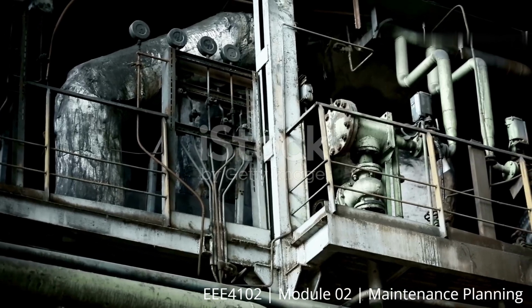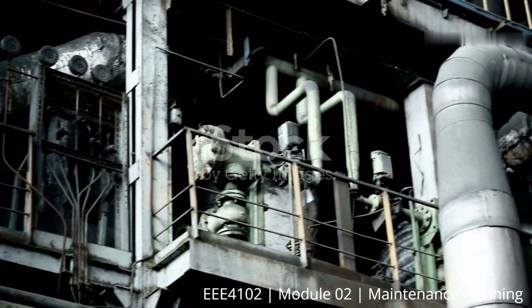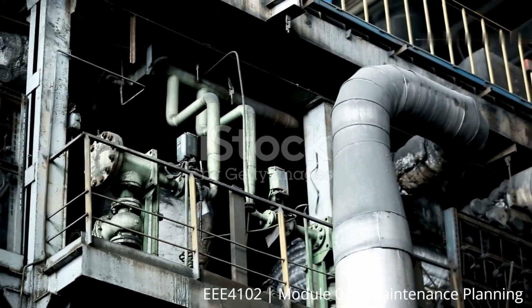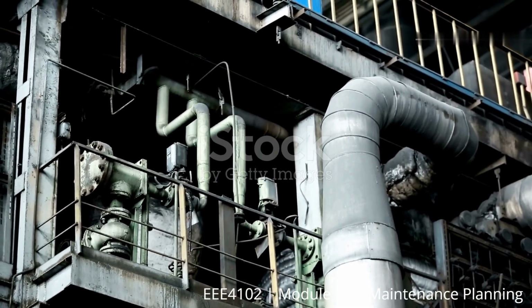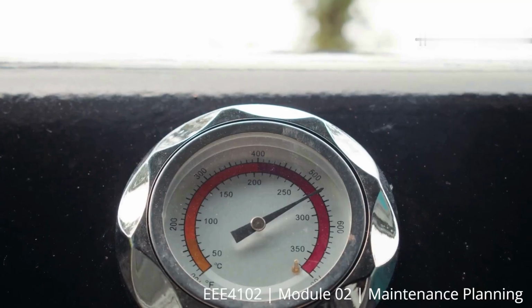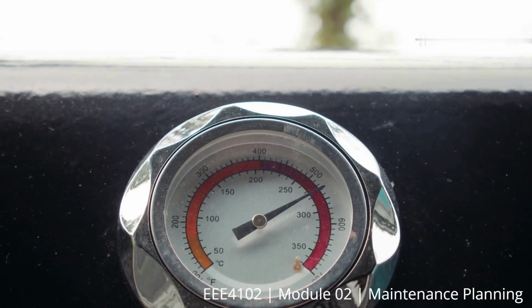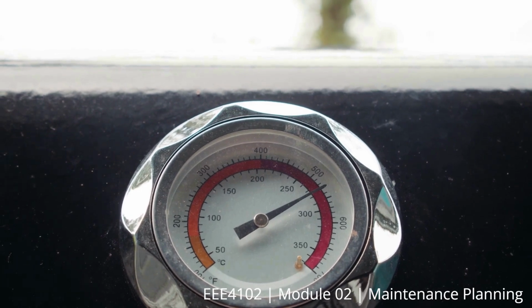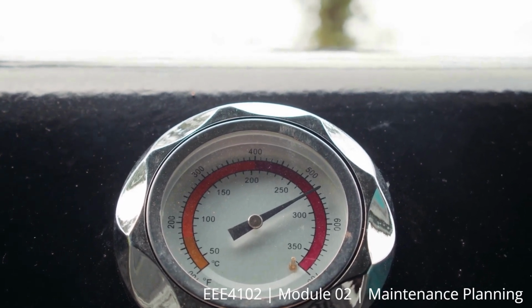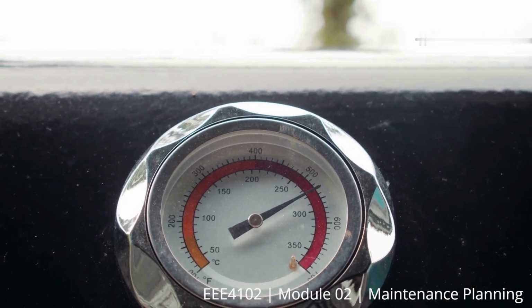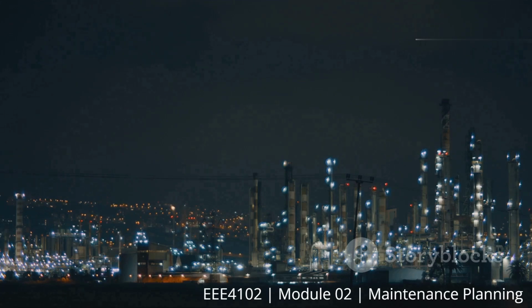Let's consider a real-world case study. Imagine a large power generation facility. During annual maintenance planning, the team deprioritized servicing a primary generator's cooling system to save time. They assumed it was low risk. Months later, a critical coolant pump failed, causing the generator to rapidly overheat, damaging its windings and bearings. The unit tripped offline, triggering an emergency plant-wide shutdown that cost millions in lost revenue and emergency repairs.